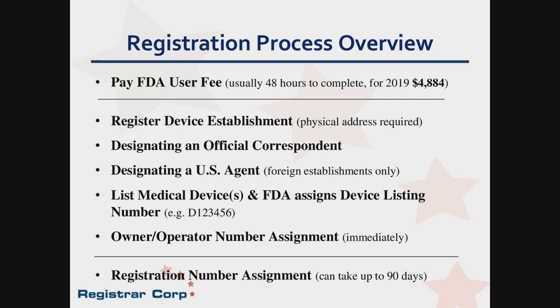The next step would be the listing of your medical devices. During that process, at the end, FDA will automatically assign what's called a device listing number. That number is very important and is used for import into the US. So you should definitely keep a printout of these numbers. Also assigned at the end is what is called the owner-operator number. And you can start doing business. You might be located in Europe and you want to send medical devices into the US. You can use your owner-operator number to start business.